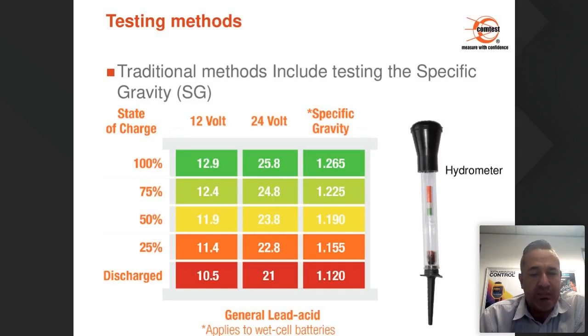The problem with that test is it's time consuming. Each cell needs to be opened. So physically, each and every little plug cell where the acid fills in needs to be opened, and you need access inside. You'll have to insert this hydrometer into each cell, and the values need to be written down manually. So every time you do the test, you have to write that down on a piece of paper. Gases from the cells charging cause health risks, and acid-resistant gloves need to be worn because we are opening the battery and we have access to the acid inside. So there are risks with that.